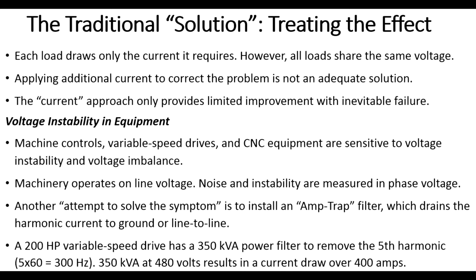So to attempt to solve some of this electrical noise, there have been various types of inductor capacitor filters called amp traps. There are other names based on brands, but they actually drain the current at the harmonic frequencies either together, which would be line to line, or all of them phase to ground to dissipate. One example of that is a 200 horsepower driven, well, the machine was an extruder for pulling material through it and holding it to size. It had a 200 horse motor. It also had a 350 kVA power filter that was trying to remove the fifth harmonic, or 300 hertz of electrical noise from the circuit.